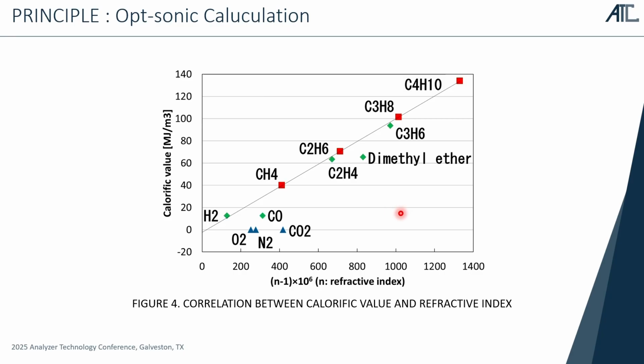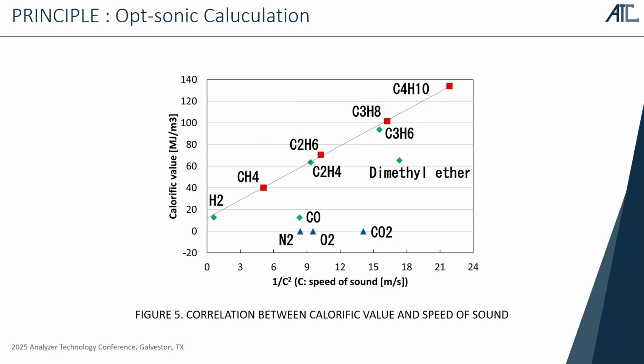So even though there is no BTU value, the optical sensor itself showed 40 megajoule, like a pure methane gas. So we had a lot of interference effect from the inert gas. And then same for the sonic sensor. We know the relationship between the sound speed and calorific value. And the same as the optical sensor, this is a sensitivity curve. It's quite linear for the hydrocarbons. But the CO2, for example, behaves as an interference gas.